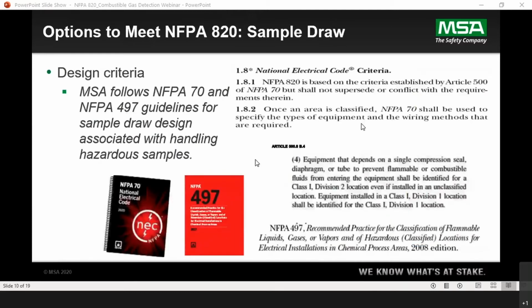So sample draw, this is kind of a key point. And what MSA does to follow NFPA 820 is we follow NFPA 70, the National Electric Code. And we also interpret and use the design guidelines NFPA 497. So 497 is basically the recommended practice for handling flammable vapors and liquids as they apply to electrical installations. So we do follow these two standards as part of NFPA 820 in our design for sample draw systems.